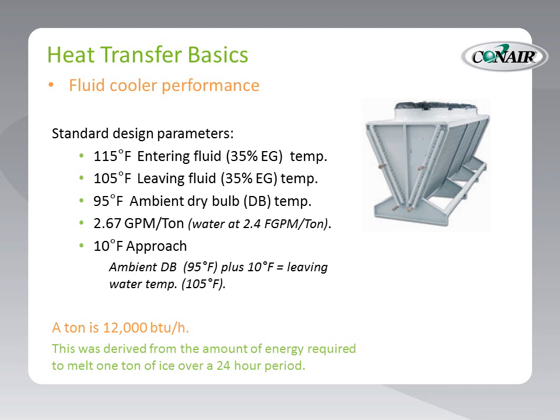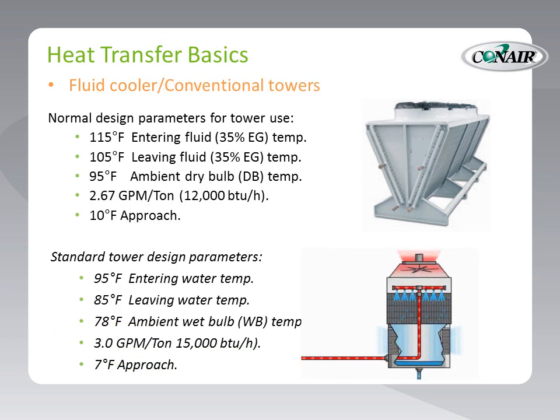So why don't we use these more often? The standard design conditions for a fluid cooler are water enters at 115°F and leaves at 105°F with a 95° ambient dry bulb, while circulating 2.6 gallons per minute of a glycol solution per chiller ton. For fluid coolers, we can expect an approach temperature of 10°F — that means we can provide a leaving water temperature 10 degrees above the ambient dry bulb temperature. Some process loads may not be able to accept fluid temperatures of 105 to 115°F, so we are not able to use this solution for such applications.